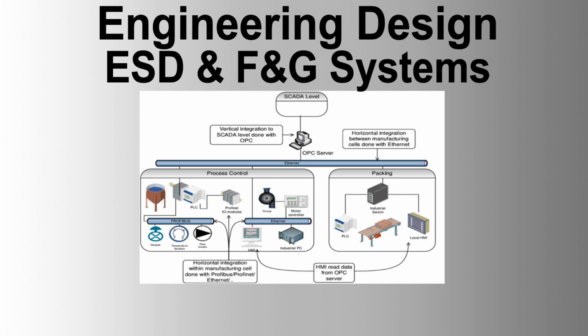4. Safety and reliability. The system must be designed to be fail-safe, with normally energized circuits. High availability in excess of 99.92%, including all equipment from input to output. Full MTBF and MTTR calculations to be provided. By adhering to these technical specifications, the ESD F&G system will provide reliable, high-integrity protection for personnel, equipment, and the environment, ensuring safe operation and quick response to emergencies.